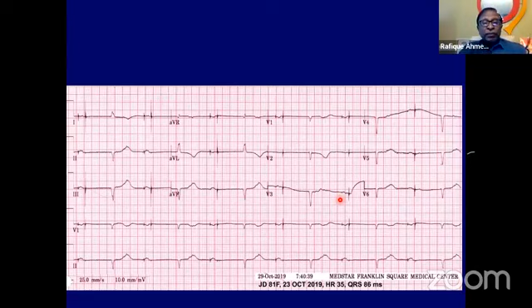This is another patient. So look at this. There is atrial pacing. There is ventricular pacing, but no capture. So what is the problem? The problem is the lead is not fractured. It is delivering a spike, but it's not adequate enough to capture. So either the threshold has gone up, or maybe the lead has perforated and gone into the pericardial space, and it's not capturing. But lead integrity itself is present because there is a spike.